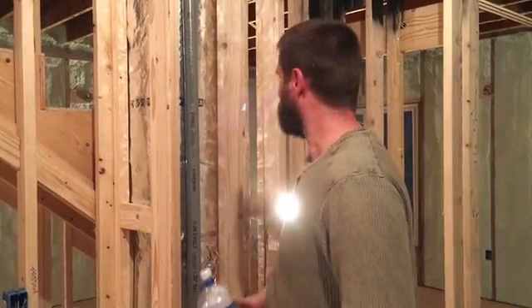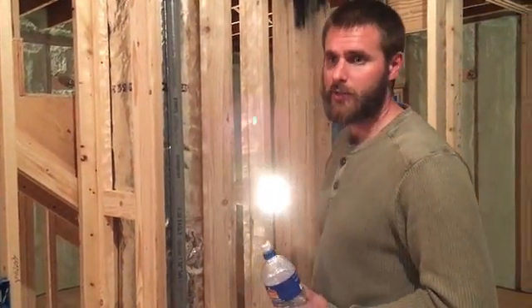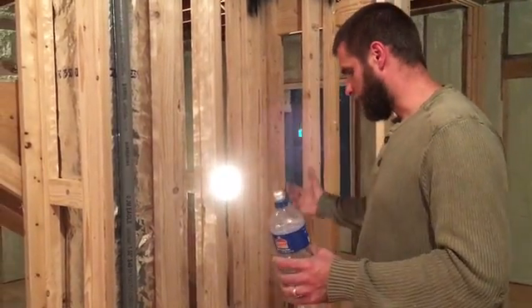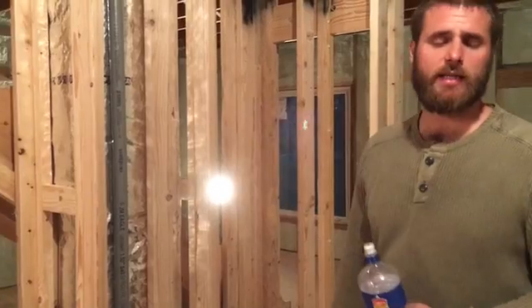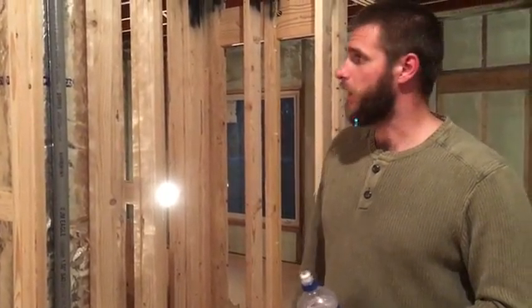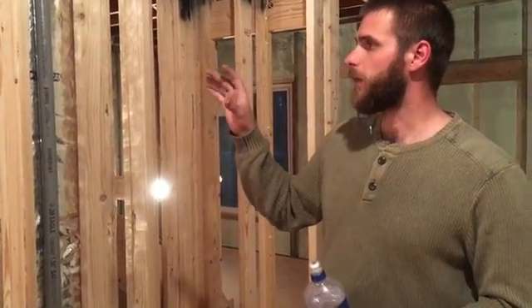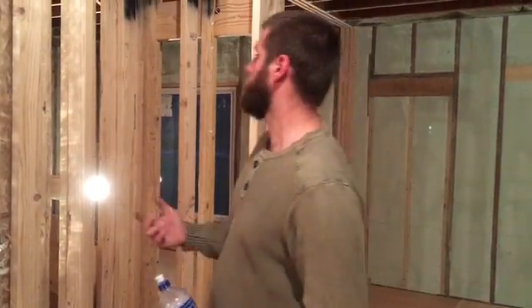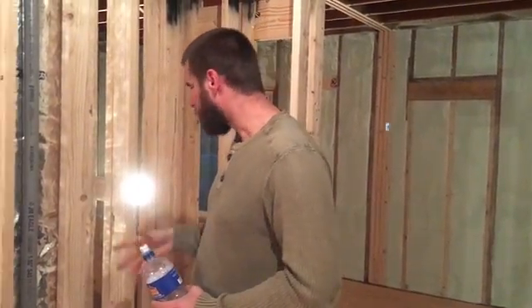I wrapped it all with insulation, taped it, masticed all the joints. If you're into efficiency and trying to do things the best you can, it's worth it, if you live in a pre-existing house, to go down to your mechanical room and look at your ductwork to see if there's any exposed sheet metal duct. Are all the joints either taped, or ideally there's a product called joint mastic or joint compound for ductwork. It's really called mastic, but it's a latex-based product, kind of like putty. You paint it on thick and it air seals the duct so you're not leaking air where you don't want. Nobody's ever going to be inside this chase, so it does no good for us to leak hot or cold air into it. So I very elaborately painted it up, and I think there's actually a blog post about that.